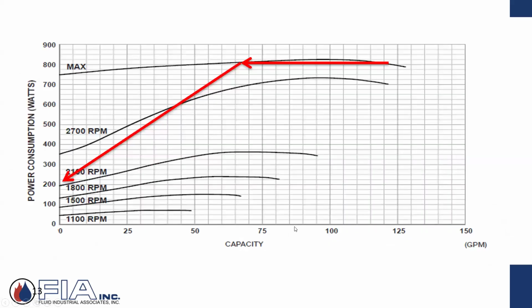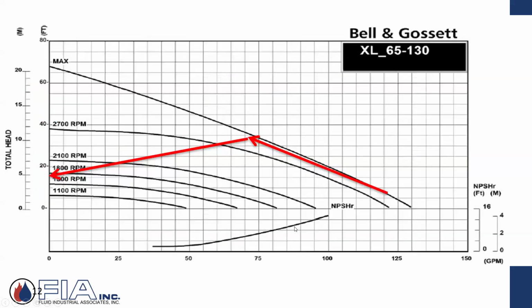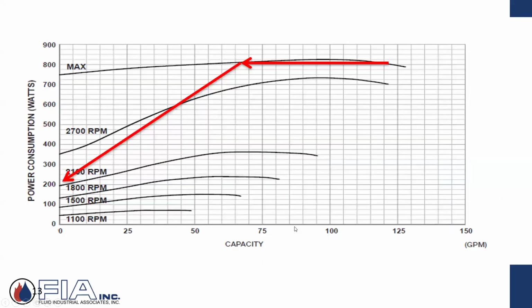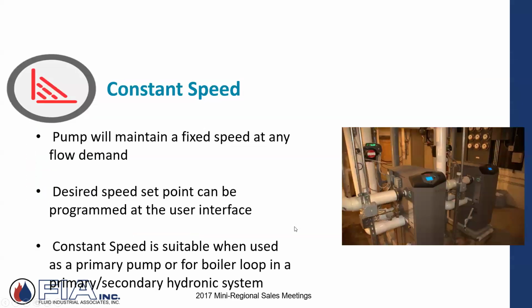You look at it and say, okay, well, whatever. Here's the interesting part. This is where the people that pay the electric bill are interested. It's the same pump, but now it's a power consumption, a watt consumption curve. For this curve, as I start to slow down the speed, as I ramp through these various speed RPM curves, look at my wattage consumption. It's pretty substantial. It's a drop. And that's the benefit to that building owner or that person paying the utility bill. It's why the utilities say, hey, with this technology, we're going to offer an incentive to upgrade your traditional on-off pump that's been there, 1.5 horse, 2 horse in an apartment building, whatever, to go to this technology. Here's the reason.